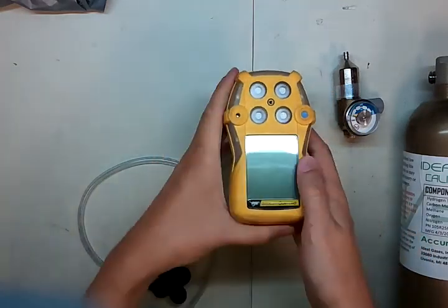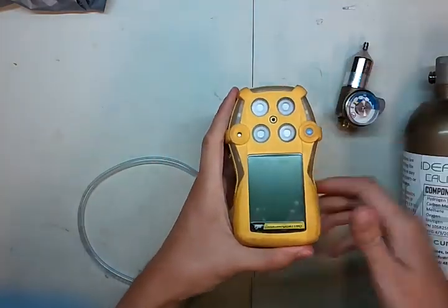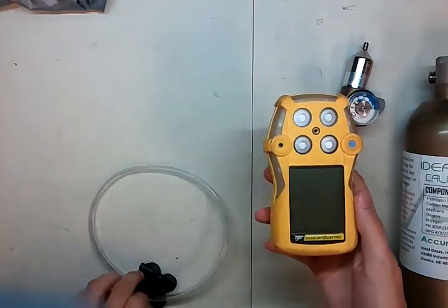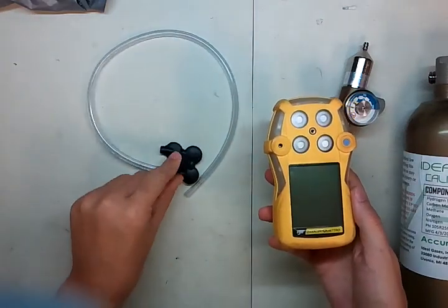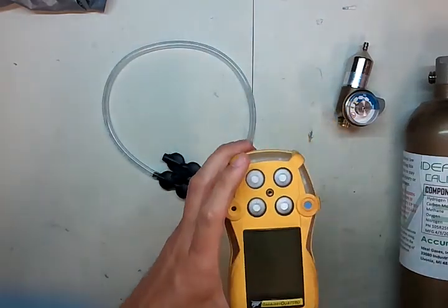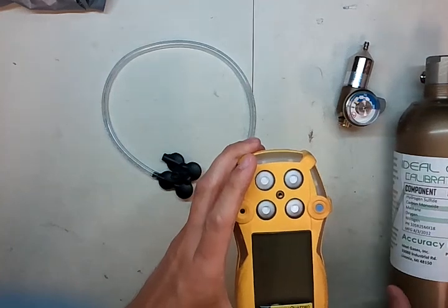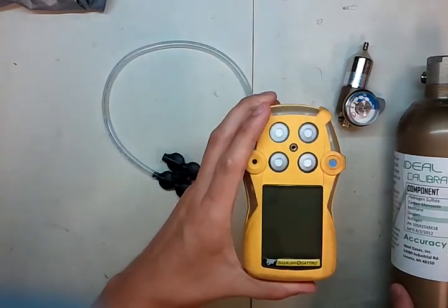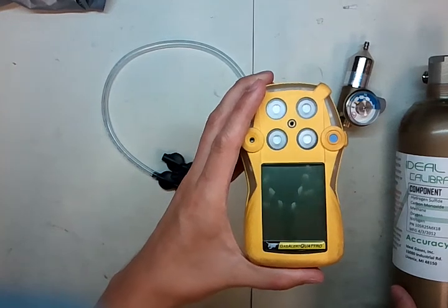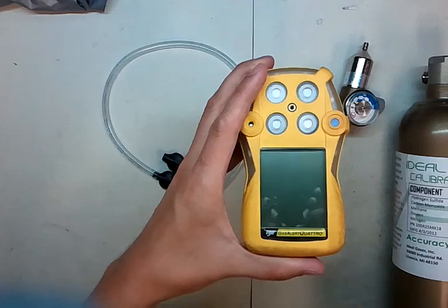Okay, first things we're going to need is just the gas monitor, calibration adapter. Here we've got some tubing and the calibration cap right here, and also some calibration gas. Cal gas for this one is 25 parts per million hydrogen sulfide, 100 parts per million carbon monoxide, 2.5% methane or 50% LEL methane, same thing, 18% oxygen with a nitrogen balance.